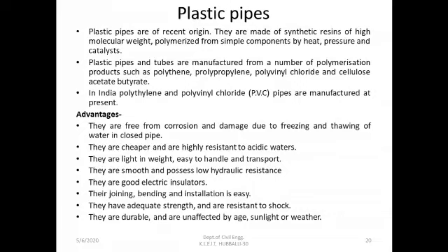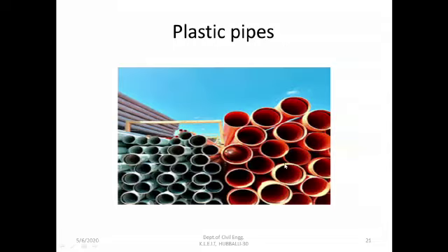They are free from corrosion and damage due to freezing and thawing of water in closed pipe. They are cheaper and highly resistant to acidic waters. They are light in weight, easy to handle and transport. They are smooth and possess low hydraulic resistance, and they are good electric insulators as well, and their joining, bending and installation is easy. They have adequate strength and resistant to shock, and they are durable and are unaffected by age, sunlight or weather. So this is the picture.